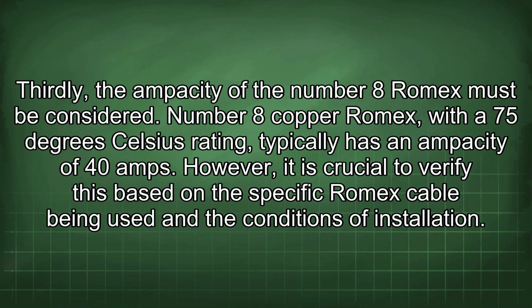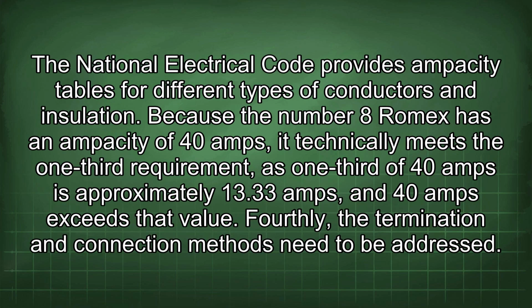Thirdly, the ampacity of the number 8 Romex must be considered. Number 8 copper Romex, with a 75 degrees Celsius rating, typically has an ampacity of 40 amps. However, it is crucial to verify this based on the specific Romex cable being used and the conditions of installation. The National Electrical Code provides ampacity tables for different types of conductors and insulation. Because the number 8 Romex has an ampacity of 40 amps, it technically meets the 1/3 requirement, as 1/3 of 40 amps is approximately 13.33 amps, and 40 amps exceeds that value.